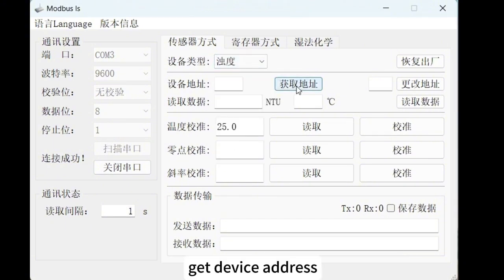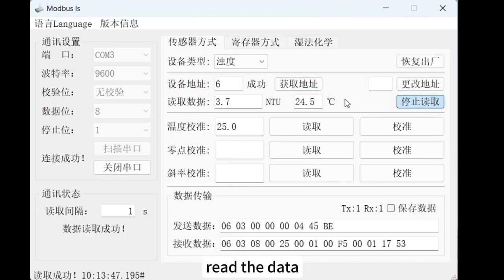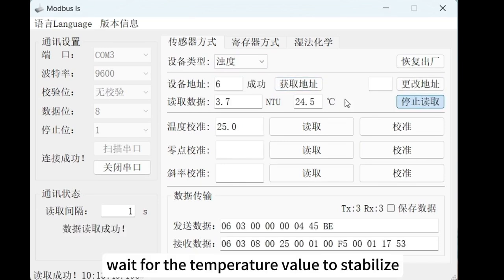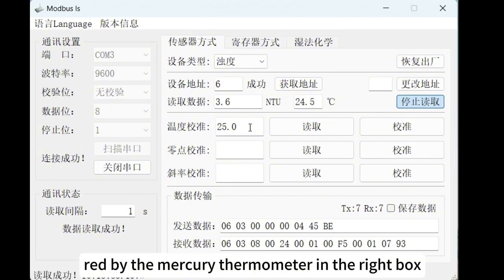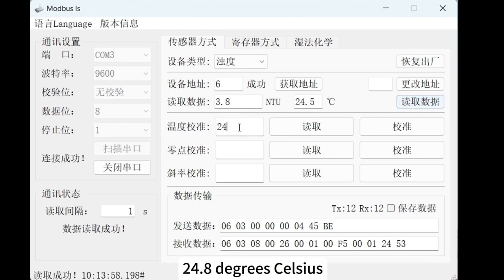Get device address. Read the data. Wait for the temperature value to stabilize. Enter the actual temperature value read by the mercury thermometer in the right box for temperature. 24.8 degrees Celsius. Click Calibrate.